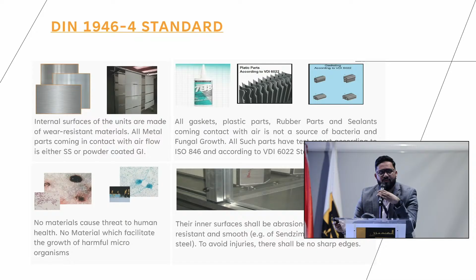Some filtration requirements: depending on class 1A or class 1B, it is defined for a DIN standard that a minimum of 2 filtration stages for class 2 and a minimum of 3 for class 1A is required, where there should be at least a pre-filter, a fine filter, and a HEPA or F9 filter at the end of the air handling unit. Another key point is how the filters used in hygienic air handling units differ. They are biostatic coated. This means the fungi or bacteria which develop in the filters do not multiply or get carried forward in the airstream of the air handling unit. For the filter area, a sizing is given that it should be greater than 10 square meters per square meter of area, and the filters are to be certified to DIN standards again.